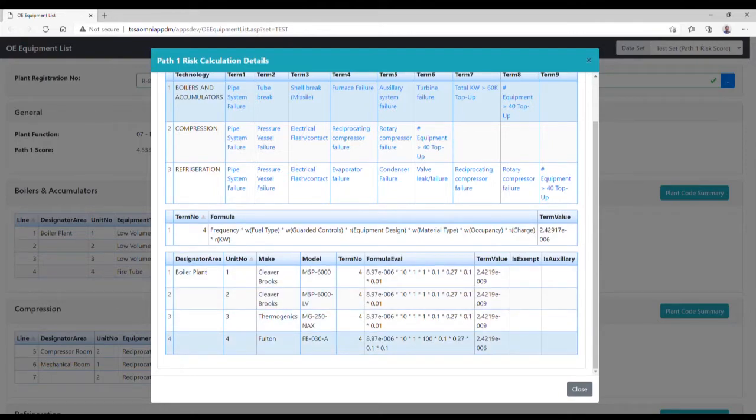Charge, so that's the gallons of fluids. That's table 14. And so there was 74, so it's just below that 75 limit. So it's 0.1. And then the power rating, if you look at table 15, so low water volume boilers get a little bit of an extra credit here. So they're all at 0.01 because they're below 1500 kilowatts. And then we have 0.1 for that fire tube boiler.